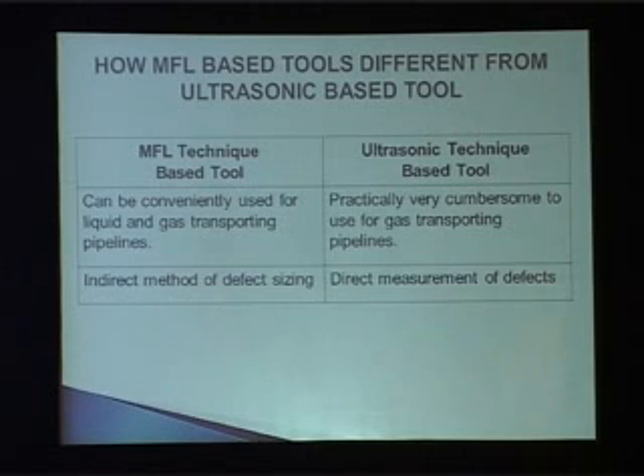We know this very well because we apply some liquid whenever we are taking the residual thickness for, let's say, any equipment. We apply grease, oil or something and then put the sensor. That scenario is not available here. The second main difference is MFL technique based tool is an indirect method of defect sizing. You see, it is based on the flux leakage. More is the flux leakage, deeper is the defect. That means what we are measuring actually out of this tool, we are not measuring the metal loss, we are measuring the flux leakage basically. And then we convert this flux leakage into the metal loss, because the tool is calibrated accordingly.